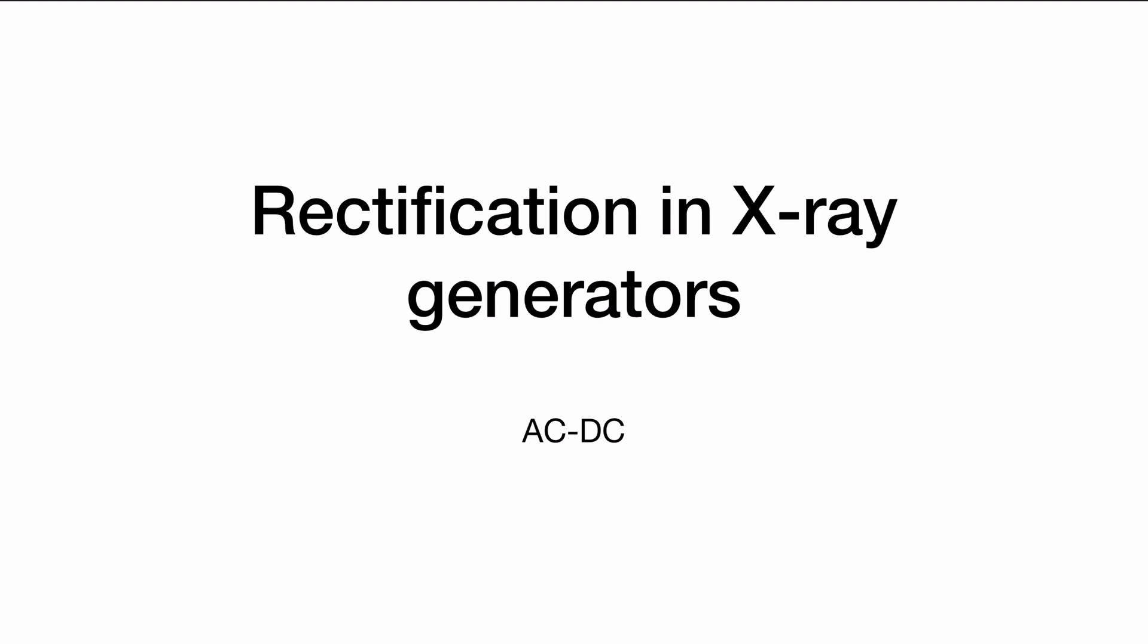Welcome. In this video, I wanted to talk about an important and necessary process in X-ray generation, in particular with X-ray tubes, and that's a process of rectification. Essentially, we are converting AC current, or AC alternating current, to DC direct current.